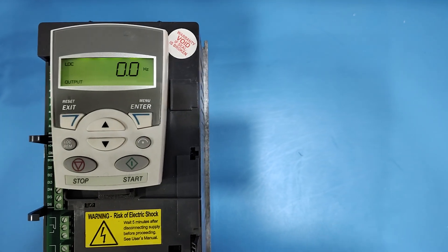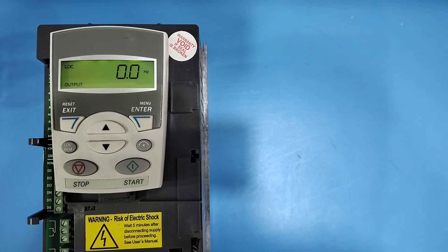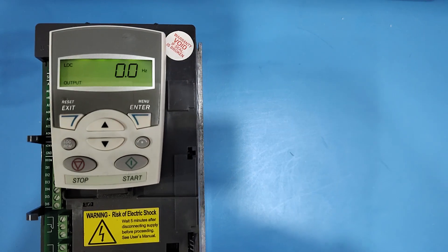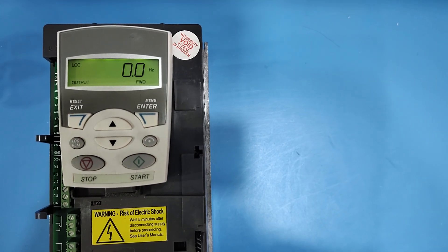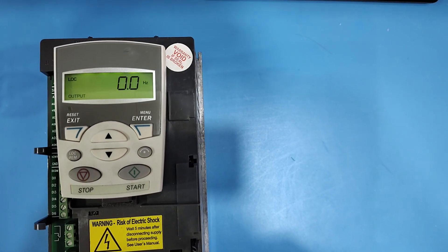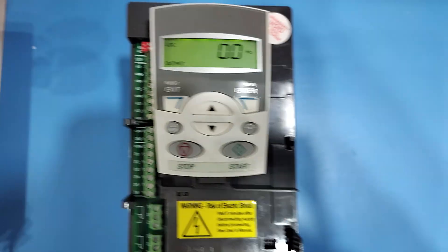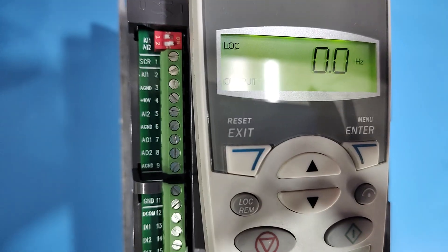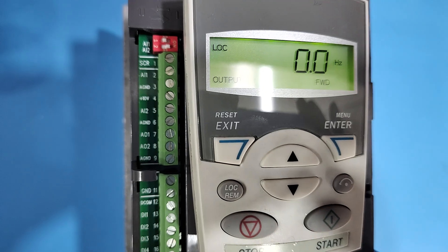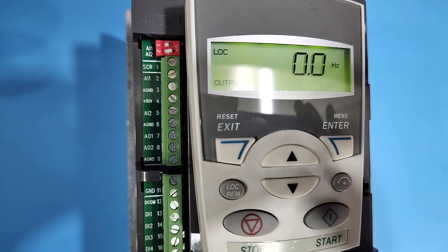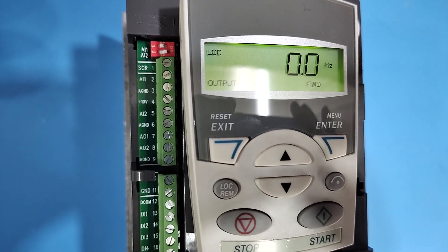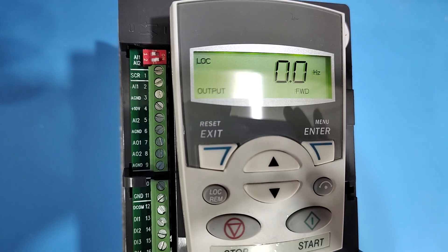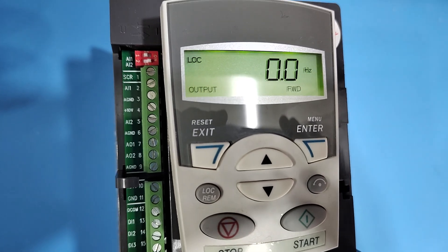Analog output function in ABB ACS 550 drive. If you want to use your analog output for programming in ABB ACS 550 drive, follow this process. In the ACS 550 drive there are two analog outputs: AO1 and AO2 — terminal 7 for AO1 and terminal 8 for analog output 2.